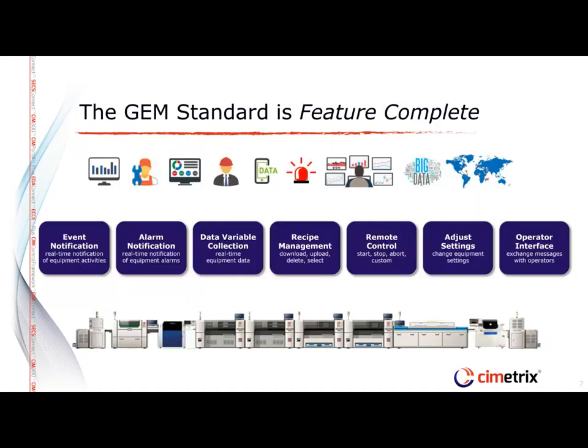GEM is a complete standard. Here is a summary of some key features making GEM successful. First is event notification — real-time notification of what's happening at the equipment, such as board in and board out events; you can also define your own events. There is alarm notification so the host can track when anything dangerous is happening at the equipment. There is also generic data variable collection for gathering data in real time, monitoring sensors, and capturing status information from hardware and software.